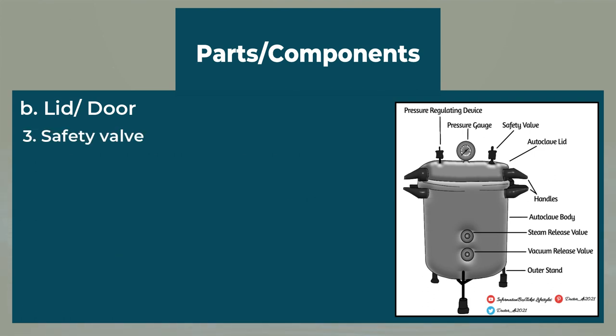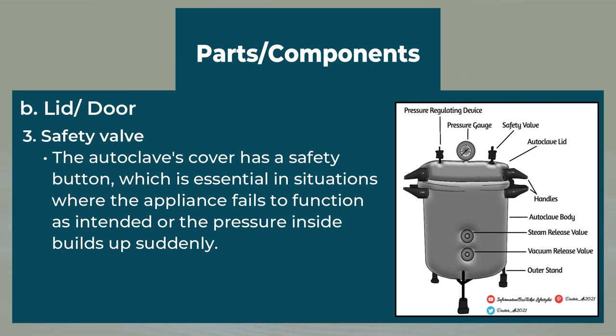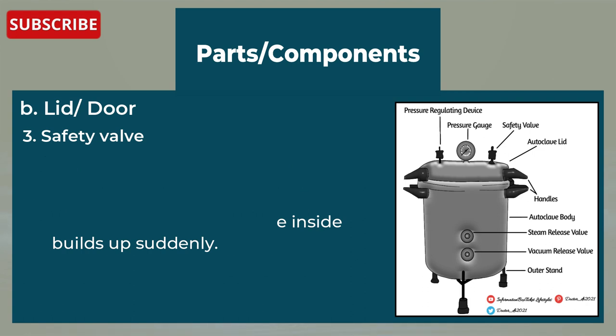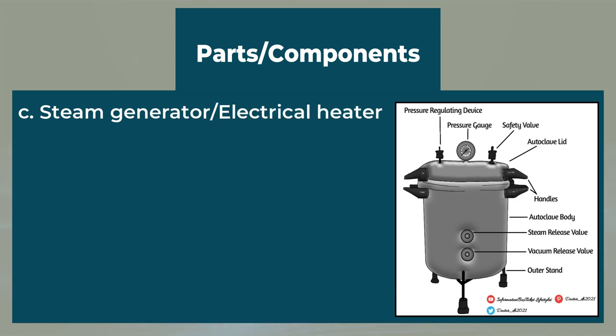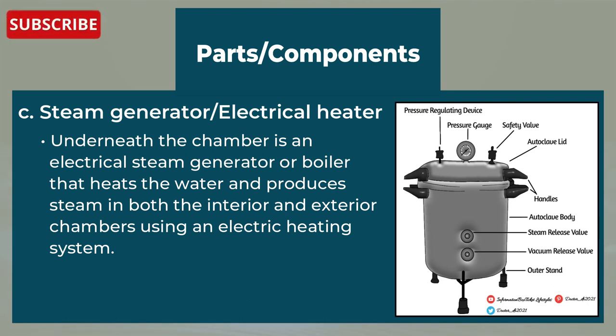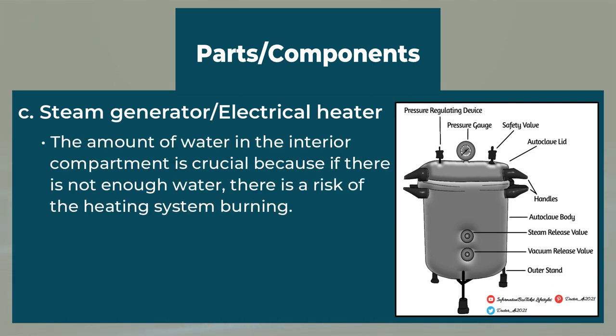The safety valve is another component on the autoclave's cover, essential in situations where the appliance fails to function as intended or the pressure builds up suddenly. A thin coating of rubber covering the valve's interior releases pressure and prevents an explosion. Underneath the chamber is an electrical steam generator or boiler that heats the water and produces steam in both the interior and exterior chambers. The amount of water in the interior compartment is crucial — if there is not enough water, there is a risk of the heating system burning, and if there is too much water, it might conflict with the trays and other items inside.